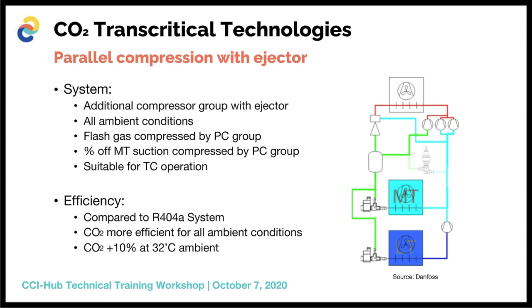The ejector effectively does free work, lifting medium temperature suction vapor into the receiver to be compressed at a higher suction pressure. With this technology, CO2 has been made energy efficient compared to any type of system and up to any ambient conditions, making it suitable for extreme high ambient conditions. At 32 degrees Celsius ambient, ten percent or more energy saving can be found compared to R404A, with even greater gains at lower ambient conditions.